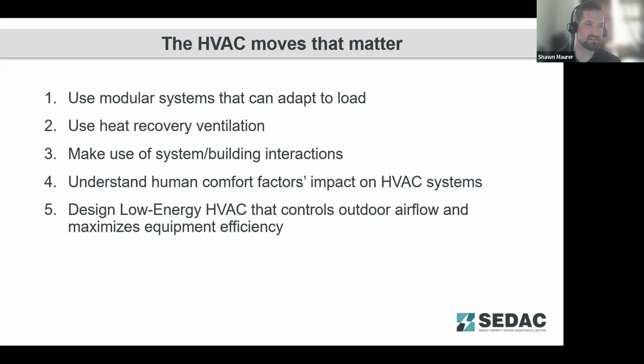Those can improve the overall operating efficiency of a chiller system. And they also have benefits for maintenance long-term in that they're easier to remove from the building without having to take out a wall of the structure or something like that to access larger equipment. Making use of heat recovery ventilation, particularly now post-pandemic when people are looking at improving indoor air quality through increased ventilation. Without heat recovery, that's going to be a significant increase in the cost of operating buildings. So looking at energy recovery wherever it's available is going to help minimize the loads on HVAC equipment and can help reduce the capacity required for those systems.